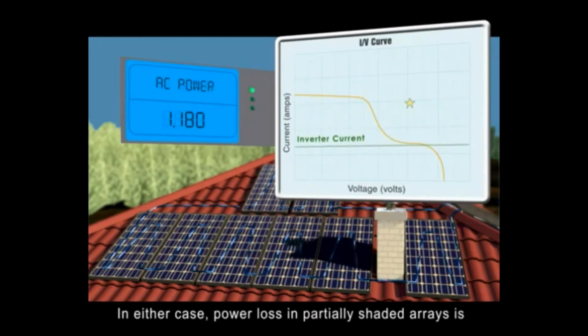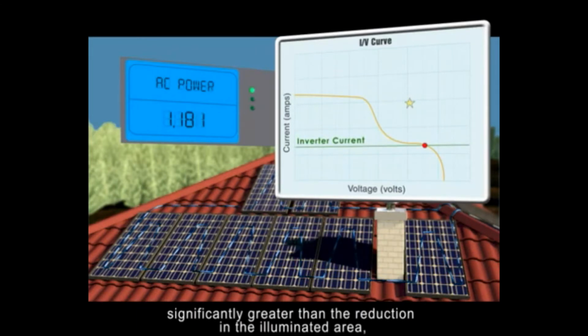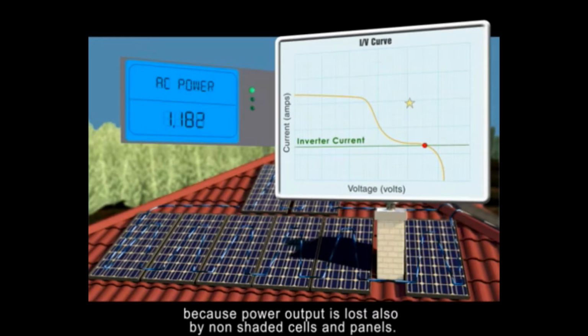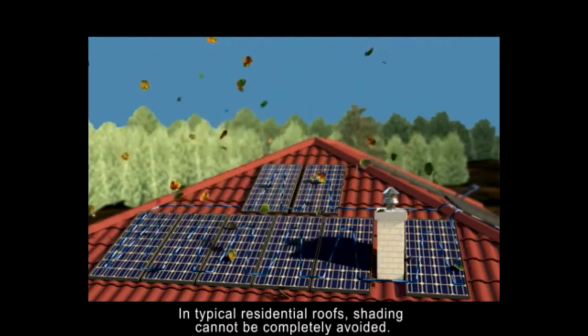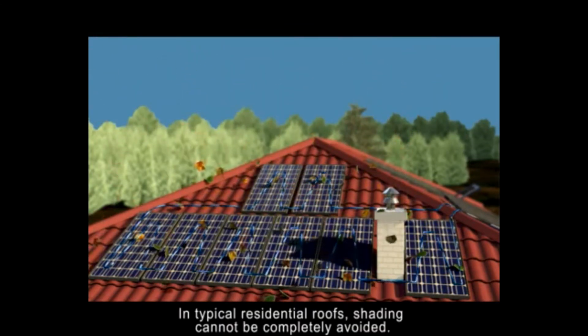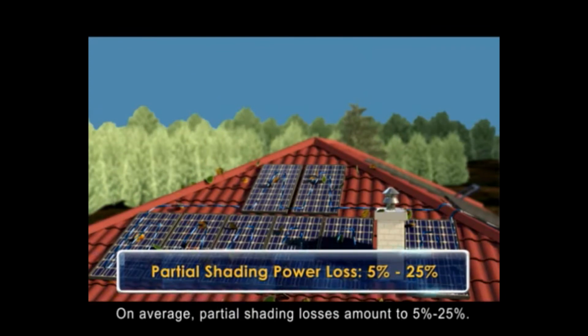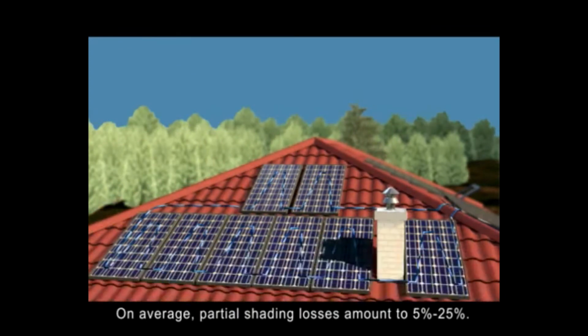In either case, power loss in partially shaded arrays is significantly greater than the reduction in the illuminated area, because power output is lost also by non-shaded cells and panels. In typical residential roofs, shading cannot be completely avoided. On average, partial shading losses amount to between 5 and 25%.